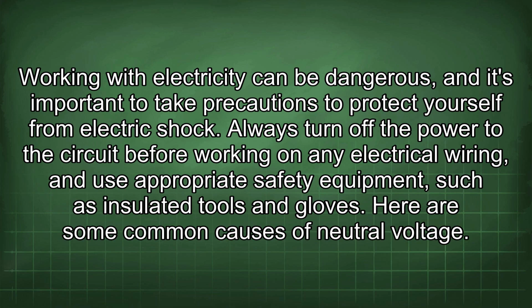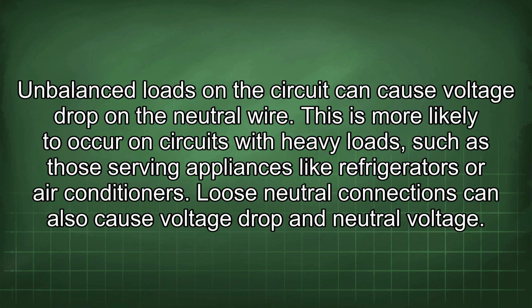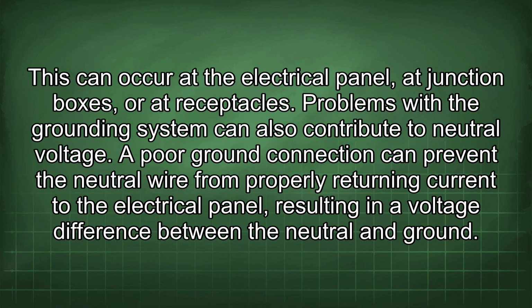Here are some common causes of neutral voltage. Unbalanced loads on the circuit can cause voltage drop on the neutral wire. This is more likely to occur on circuits with heavy loads, such as those serving appliances like refrigerators or air conditioners. Loose neutral connections can also cause voltage drop and neutral voltage. This can occur at the electrical panel, at junction boxes, or at receptacles.